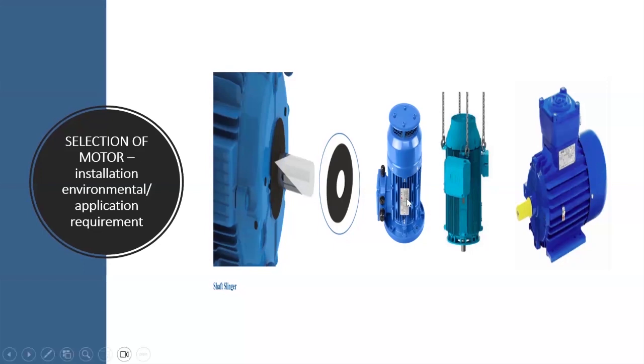And for those which are vertically mounted with the cowling or the fan facing to the atmosphere, it's expedient we get a motor with a rain hood so that rainwater and particles coming from the atmosphere do not get direct contact to the shaft, and by so doing cause the bearing to fail. So based on application, the right motor is selected, and also an explosive proof motor based on the environment, whether it's a hazardous area. So based on the hazardous area classification of the area, you know you are buying an explosive proof motor for a zone 1 area or a zone 2 area or a zone 0 area.